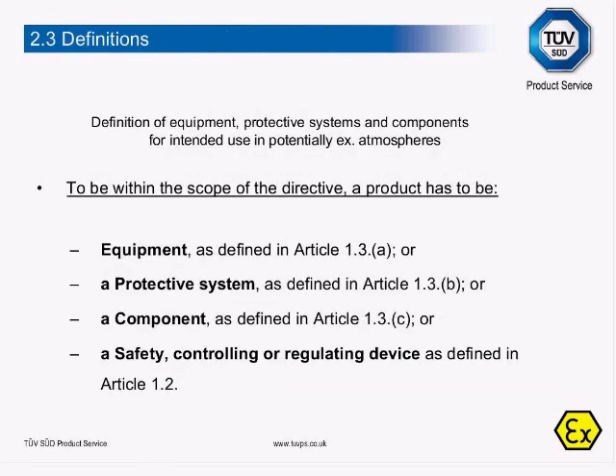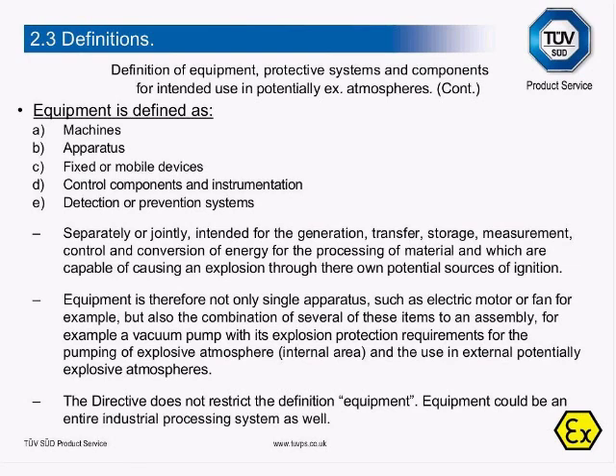Definition of Equipment, Protective Systems and Components for Intended Use in Potentially Explosive Atmospheres. To be within the scope of Directive 94/9/EC, the product has to be one of the following: Equipment, a protective system, a component, or a safety, controlling or regulating device. Equipment is defined as machines, apparatus, fixed or mobile devices, control components and instrumentation, detection and preventing systems — separately or jointly intended for the generation, transfer, storage, measurement, control and conversion of energy for the processing of material — and which are capable of causing an explosion through their own potential sources of ignition.